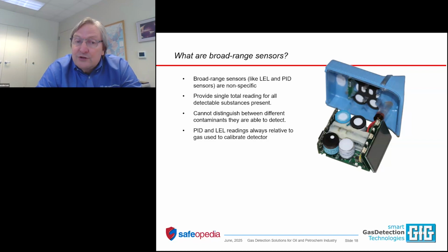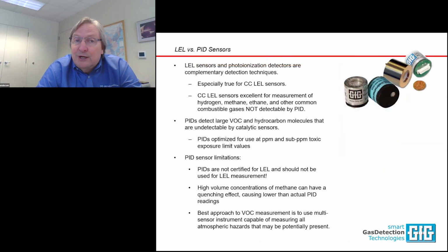The readings are always going to be relative to the gas that is used to calibrate the detector. So if you calibrate the combustible LEL sensor on methane, the readings are in methane units of measurement, or pentane scale units of measurement. For PIDs, most generally, you're going to calibrate the instrument to isobutylene. So the readings will be given in isobutylene scale increments, ppm isobutylene equivalents, or sometimes in the display we will say PID units, and the PID unit is set by the gas you use to calibrate.